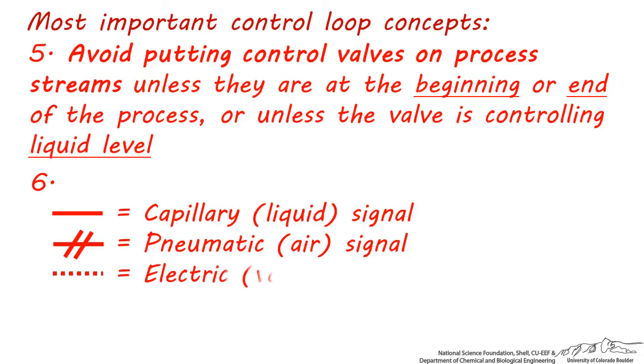Recall that a capillary or liquid signal is a solid line, a pneumatic or air pressure signal is designated as a line with hash marks, and an electric or voltage signal is designated with a dashed line.